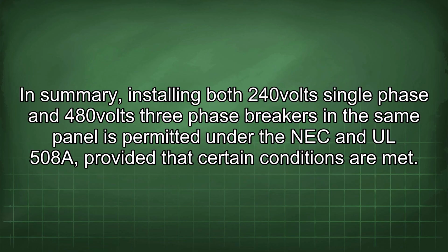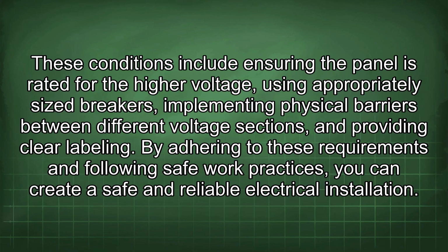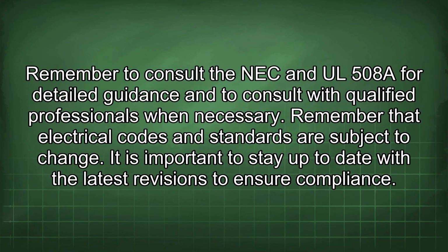In summary, installing both 240V single-phase and 480V three-phase breakers in the same panel is permitted under the NEC and UL 508A, provided that certain conditions are met. These conditions include ensuring the panel is rated for the higher voltage, using appropriately sized breakers, implementing physical barriers between different voltage sections, and providing clear labeling. By adhering to these requirements and following safe work practices, you can create a safe and reliable electrical installation. Remember to consult the NEC and UL 508A for detailed guidance and to consult with qualified professionals when necessary.